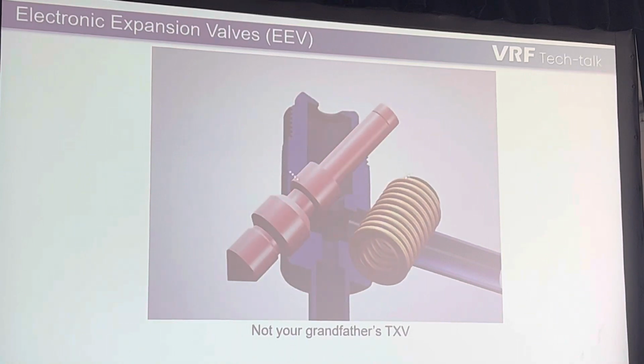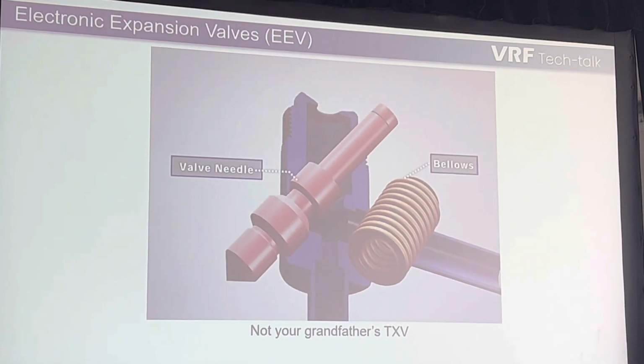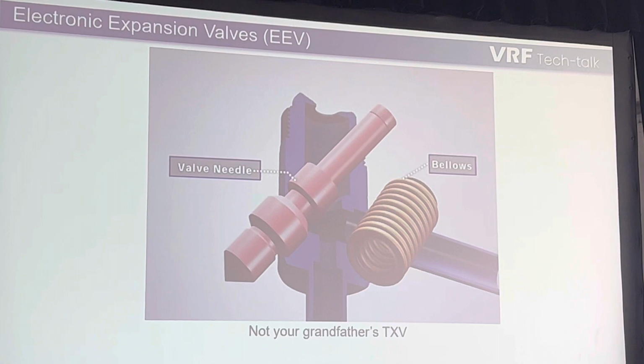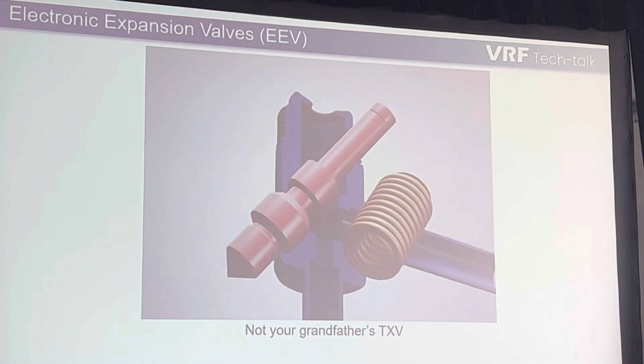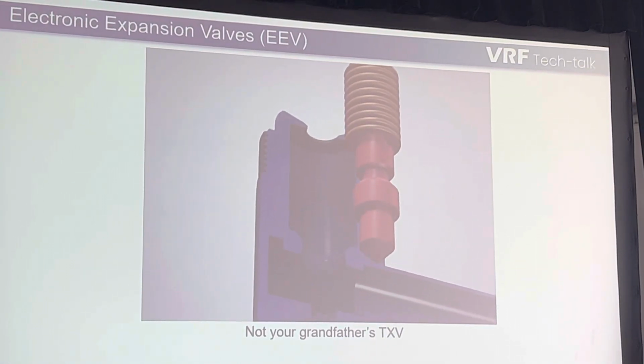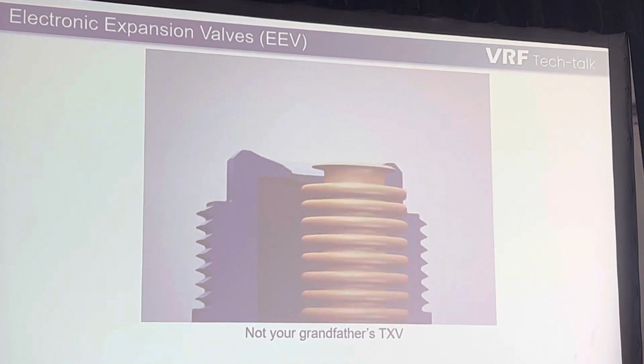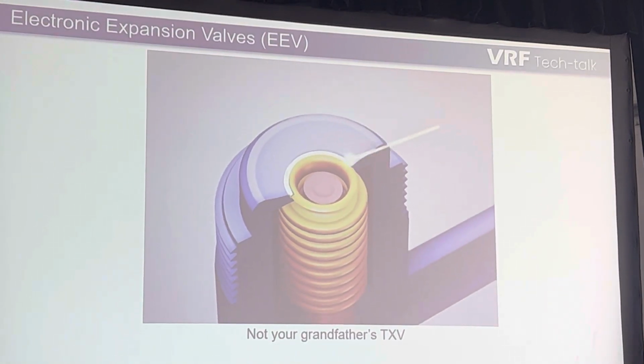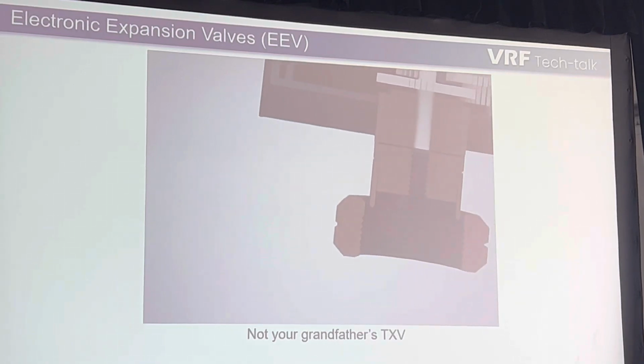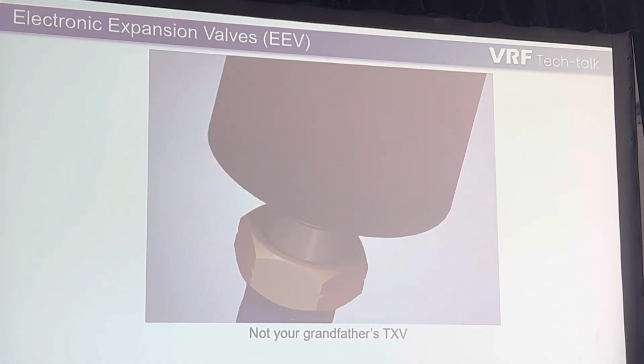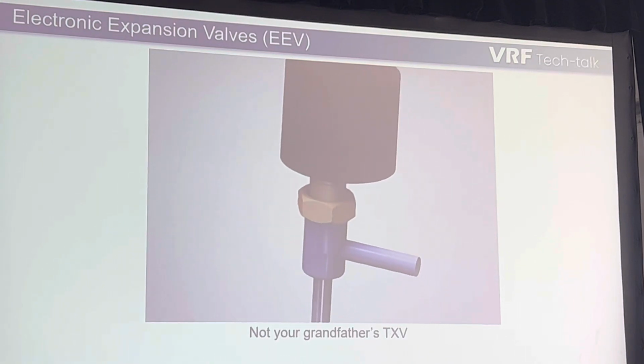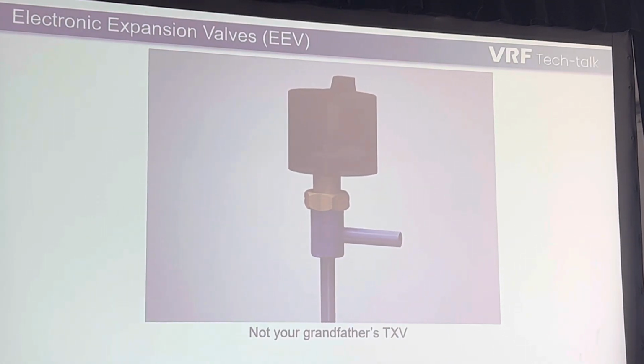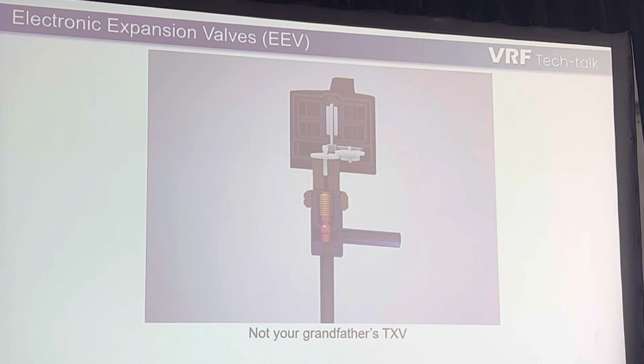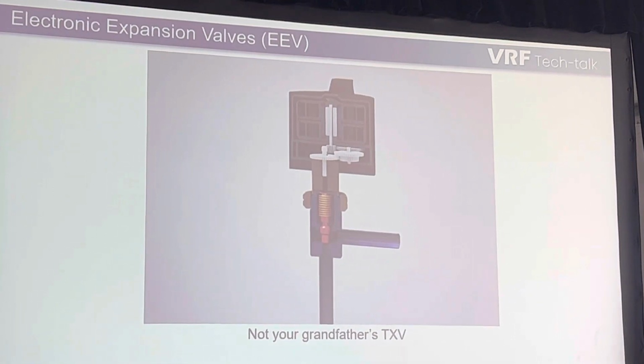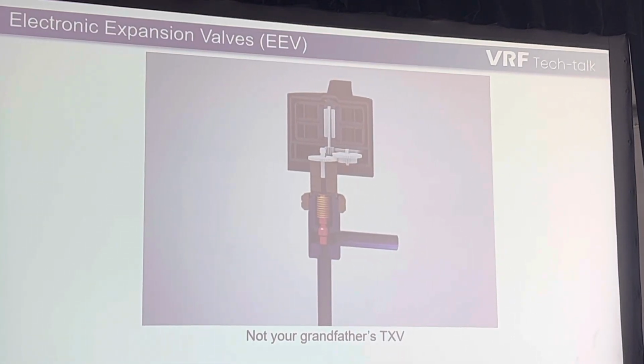As you can see, this is our body housing. You've got your valve needle and your bellow. Valve needle is what comes in contact with the refrigerant. Your bellow is what the separation between the two is. Think of it as a giant spring. This is an isolated and sealed valve, so you can remove the top of this valve to service and inspect it. Come to our installation and troubleshooting, or our service and troubleshooting class, we talk about how to diagnose these as well as service these. As you can see, these are all the major components when we're talking about electronic expansion valve.